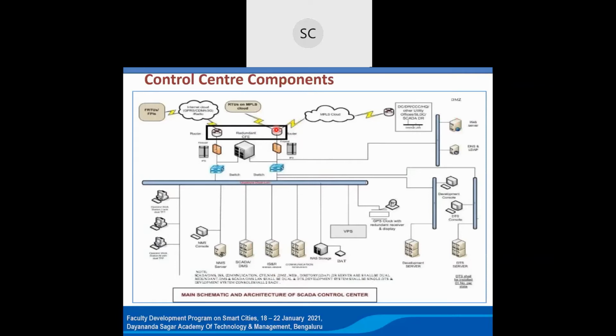Now coming to field devices. These field devices, like FRTUs, fault passage indicators, or substation RTUs (remote terminal units), communicate first to the control center communication front-end processors through various communication modes. Sometimes in the FRTUs, field remote terminal units, we use GPRS, 3G, or radio networks. In substations, we use either our own dedicated fiber network or service providers' networks like BSNL or Airtel. That data, if through third-party service providers, comes through the cloud to the control center via front-end processors. This is the overall broader view of distribution automation.